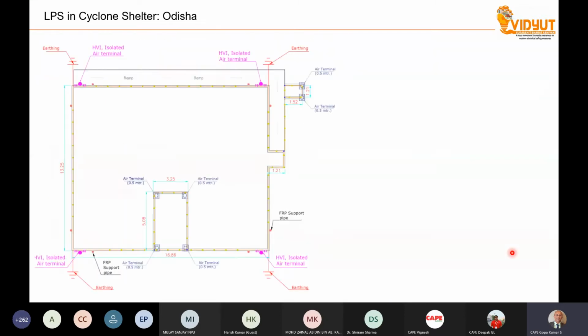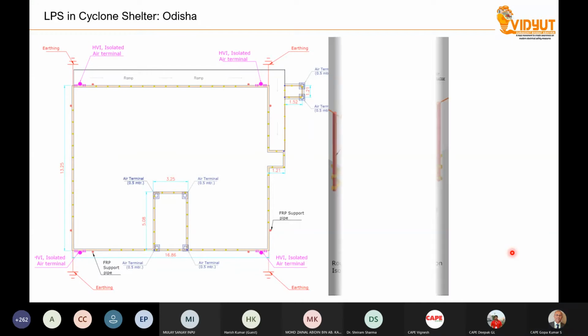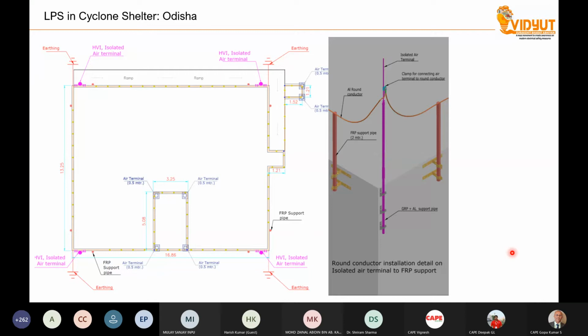Another case, a cyclone shelter in Orissa. This is the tender document. I have a picture I will show you. It's a normal RCC building, probably 7 to 8 meters high, or maybe 10 meters. You have to understand that people inside an RCC structure are protected. People inside a substantial building are protected, provided the metallic plumbing system and the metallic power lines are connected to the equipotential bonding system. So lightning protection, air termination, down conductor, and earthing is required for this building, not to protect people, but to protect the building itself.